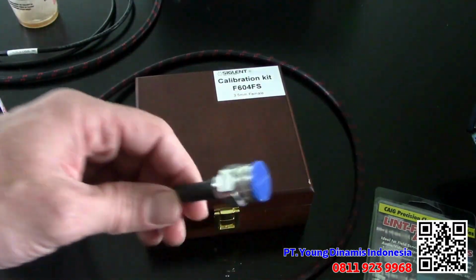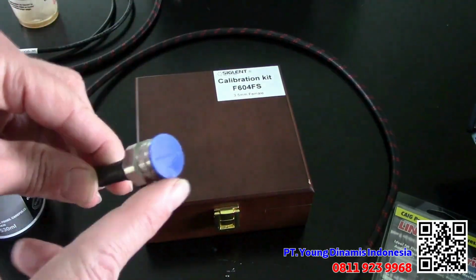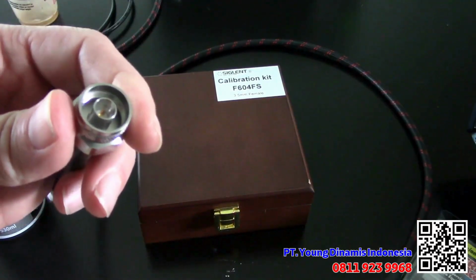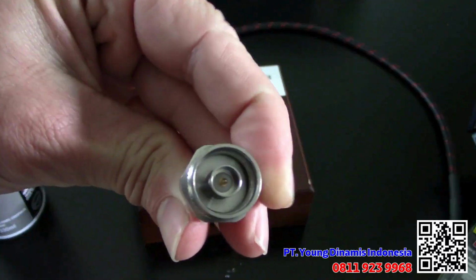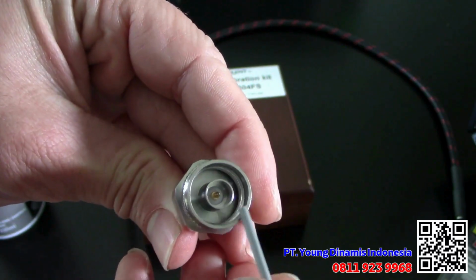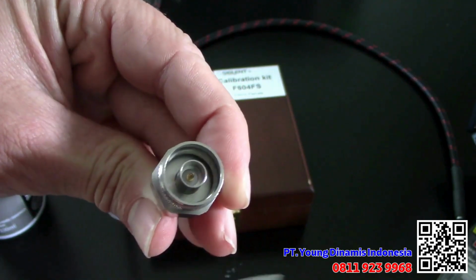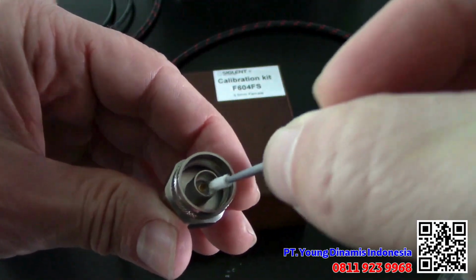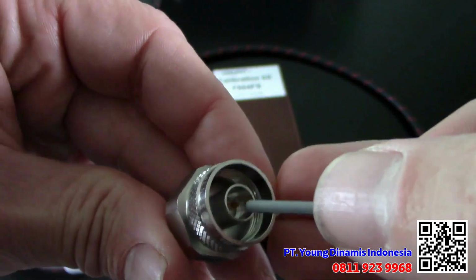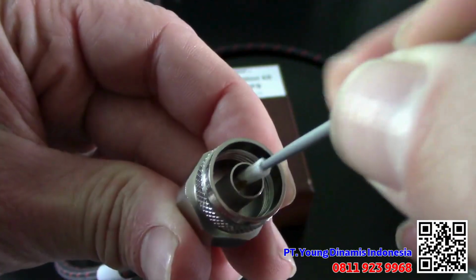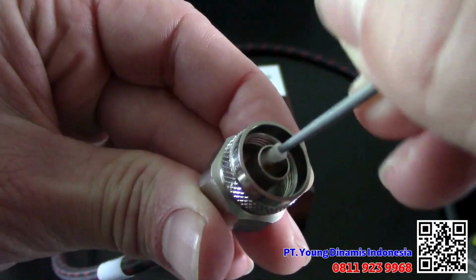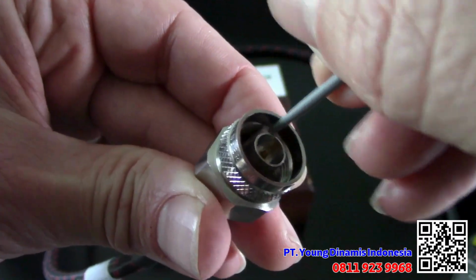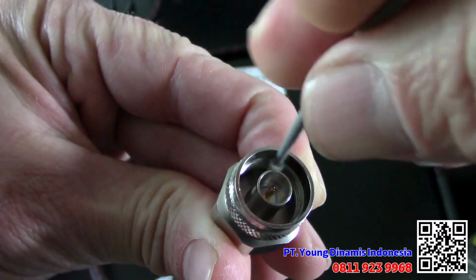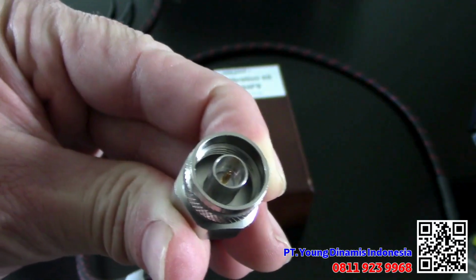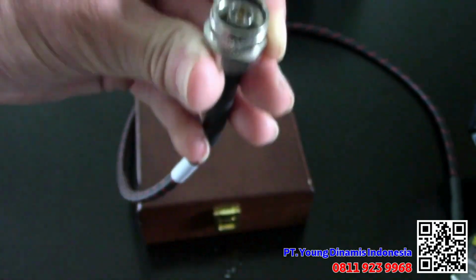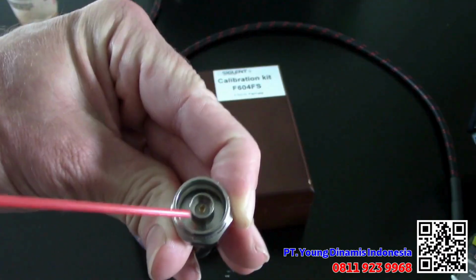When we go to our cable, in this case we're looking at an N-type connector. We can also pull that cap and you'll see we've got that center conductor, which is gold color or copper color. And then we've got the dielectric around that as well as that ground plane. And so we're going to want to clean all of those surfaces. Again, we'll have that swab. We're going to go around the center conductor and dielectric. And we want to check and just make sure that center pin is aligned and in the center. And we can then clean around. We can swirl that swab as well. And we can clean that inner thread and the inner mating surfaces just to make sure that we don't have any dust or any big particles in there as well. Quick observation visually. And then we can hit it with that compressed air again just to get rid of any dust that we might have knocked loose. And we can replace the cap if we need to.